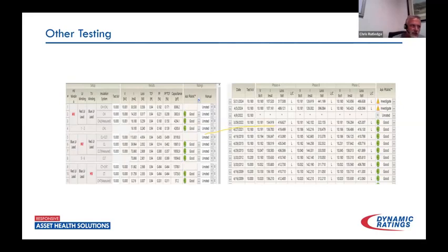So with the excitation test, of course, the more windings we're involved, the higher that voltage is going to be, thus the higher the amperage. I would be curious to see how that changes. And I got a feeling once they do this testing, we'll narrow it down to likely a PA failure, which eventually is going to lead to a complete failure of the transformer if not addressed.